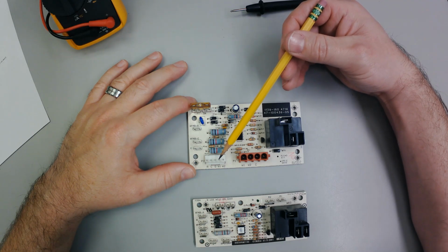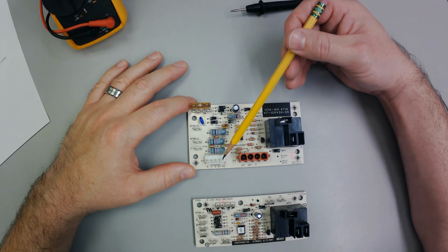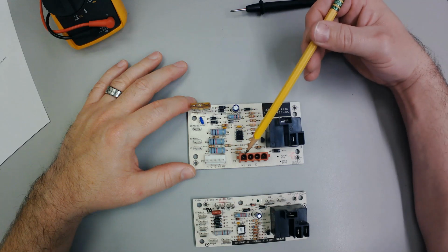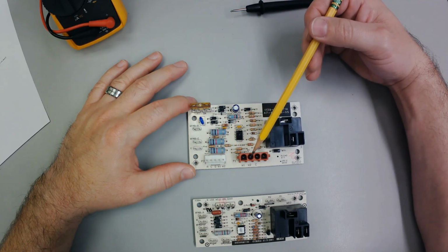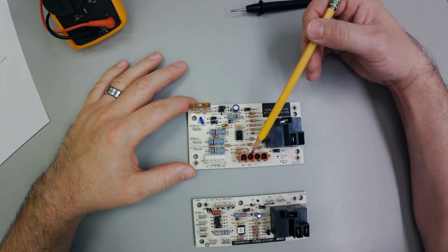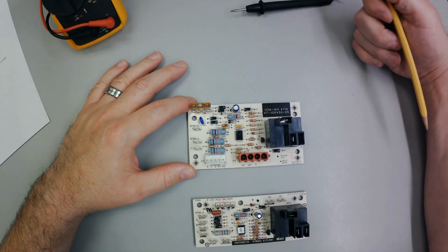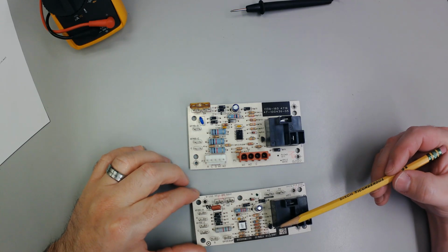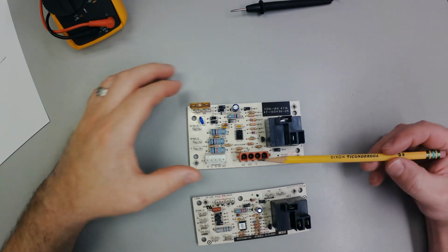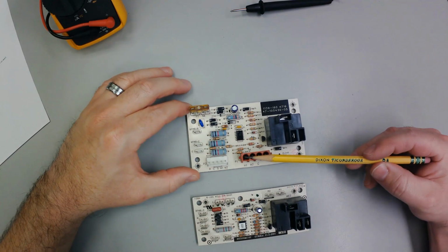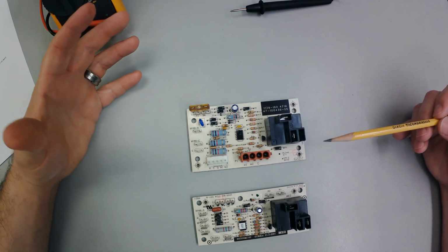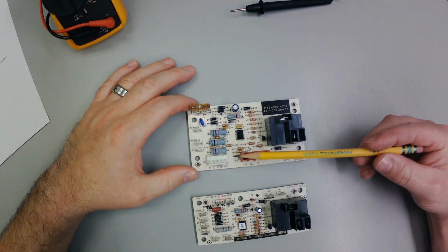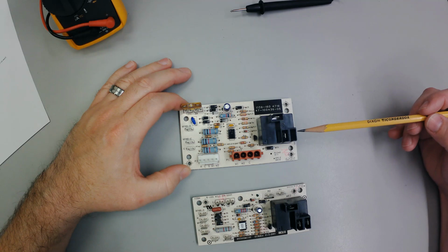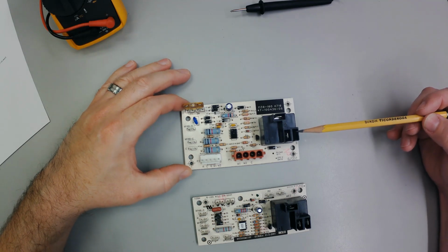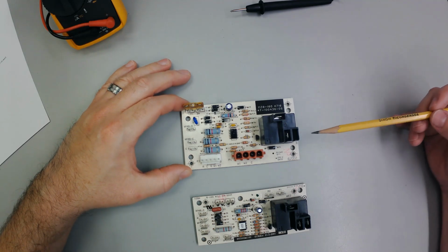Anytime that I see W on this board, when it comes in here, as W loops around and goes back out to the actual sequencer, I know to close that relay and turn the fan on. Goodman doesn't have a W on their board, and it's because you don't need it. I don't need a W on this board to run the heat. This is a fan board, for God's sake, right? So why would I have a W here and be missing a terminal off my fan relay? It's simple. They're connected somehow, right?